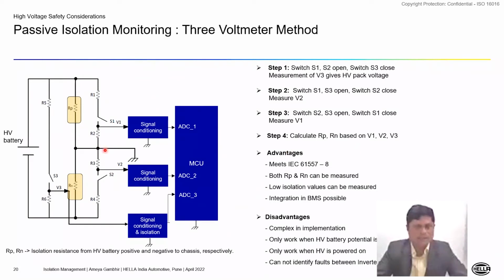In the next step, we close switch S1 and measure the voltage between HVDC plus and chassis. Based on this, and considering that RP and RN are unknown values, we try to estimate these values using internal equations. Then we compare these values with the regulatory requirement. For example, if you are using a 96 volt battery pack and the regulation says your isolation resistance cannot go below 10 kilo ohms, you can have a safety margin and then raise an alarm.